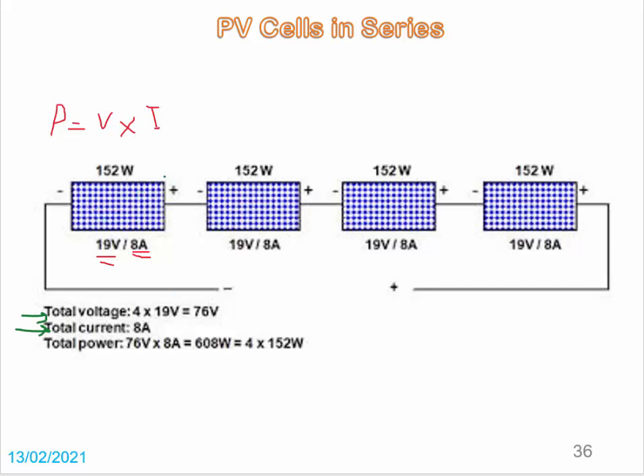The total power is the sum of the power of all four panels: 4 multiplied by 152 equals 608 watts. We can verify this as total voltage multiplied by total current: 76 volts multiplied by 8 amperes also equals 608 watts.